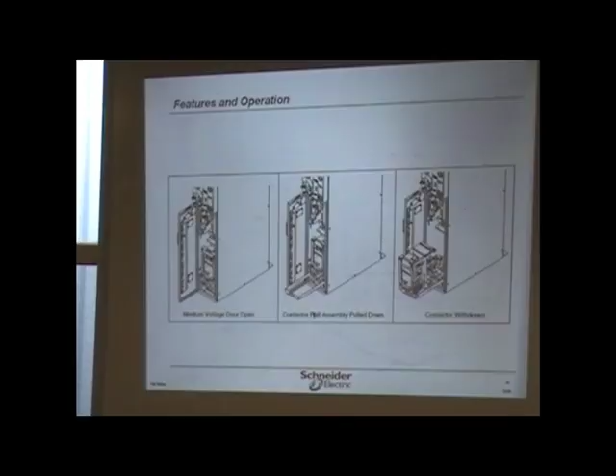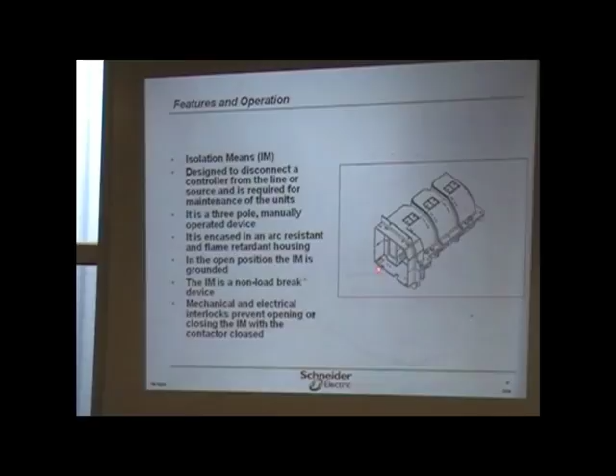Arc resistant and flame retardant housing. And in the open position, the IM is grounded. The IM is a non-load break device. Okay? That means you need to make sure that downstream there's no load on it. So here again, we're talking about making sure that no load is on it. Mechanical and electrical interlocks prevent opening or closing the IM with the contactor closed. Ooh, that's a misspelling. But essentially what it's saying is you cannot open or close this with the contactor being energized. If the contactor is energized, it's not going to allow this to open or close. So the contactor has to be de-energized before you can open or close this.